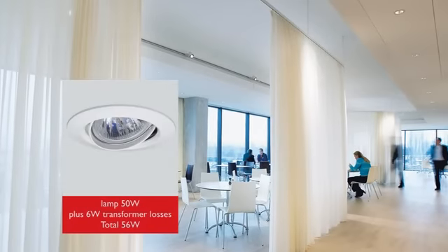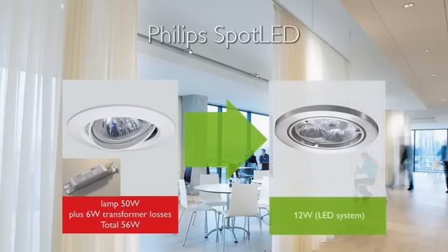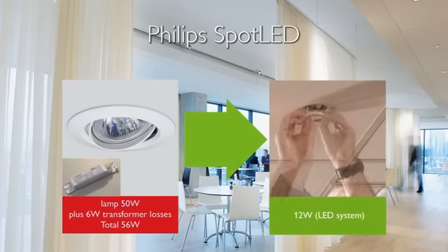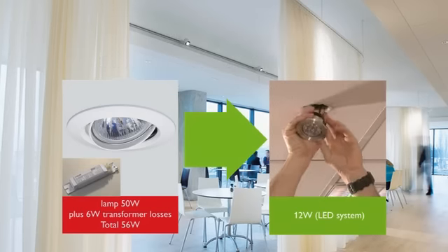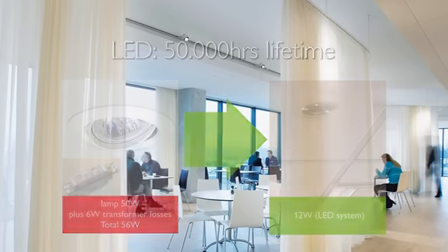Another example are the traditional dichroic halogen spots with electromagnetic transformer, which can also be replaced with Philips Spot LEDs, reducing energy consumption from 56 watts to 12 watts, saving 80% of energy. An additional benefit is the huge gain in lamp lifetime, from 2,000 hours for the halogen lamp to 50,000 hours for the LED solution.